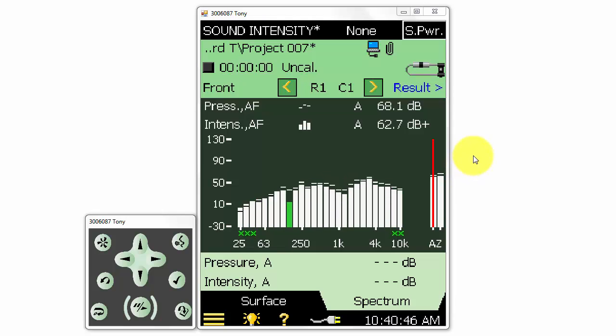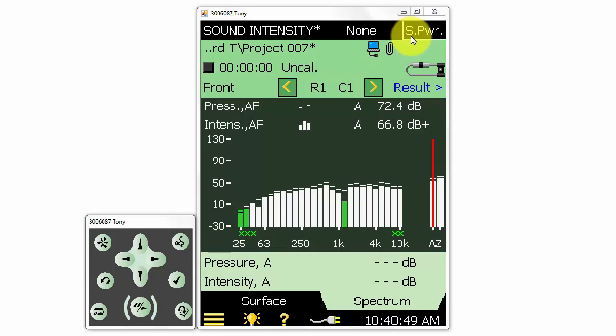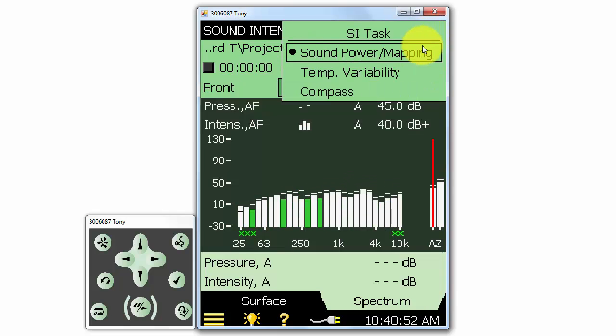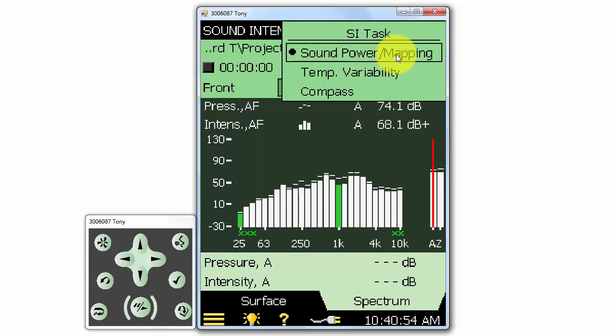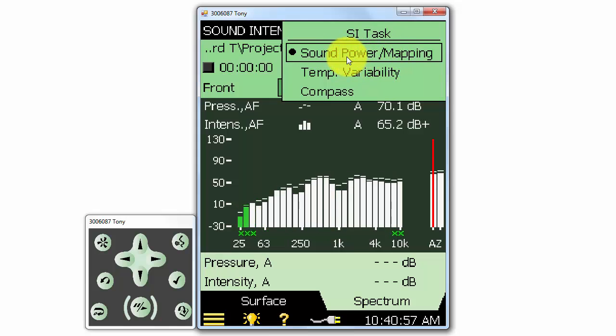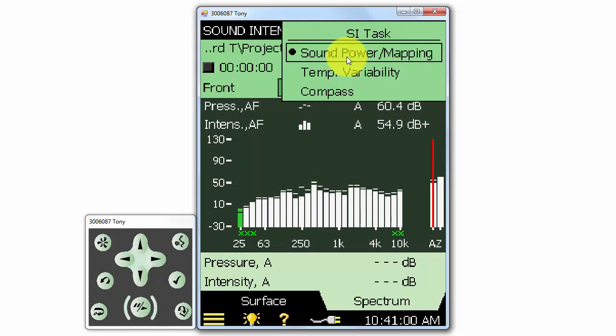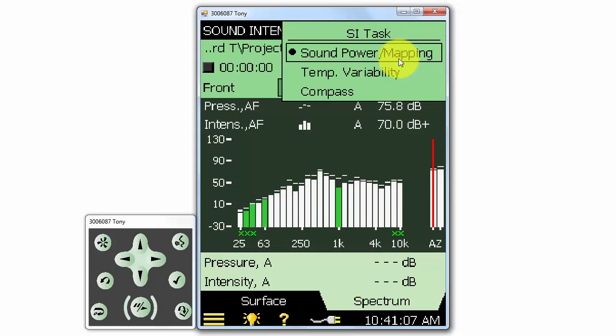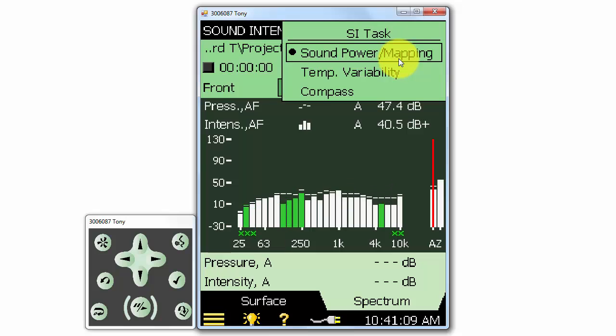In the 2270 sound intensity application, there are three main modes that we can select at the top right. First is the sound power and mapping mode, which we can use to calculate sound power to a variety of selectable ISO standards, or we can create a sound map with sound intensity measurements. The map can be shown over a picture of the test object directly on the meter, and we can do both of these at the same time.